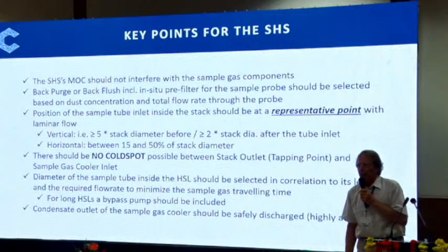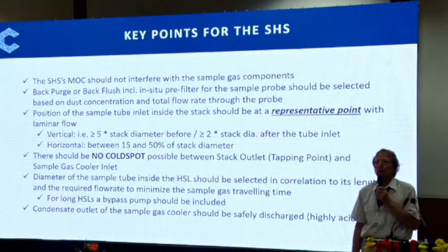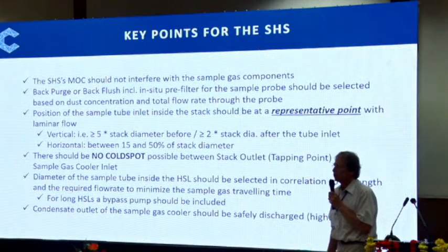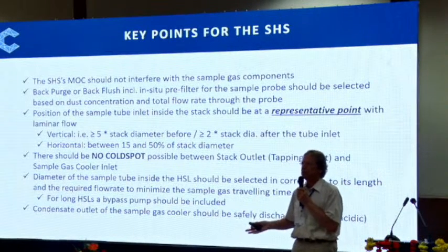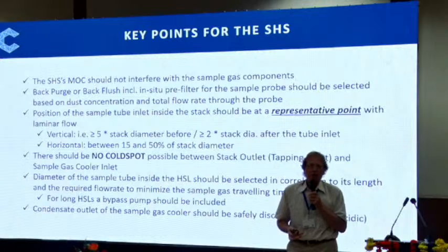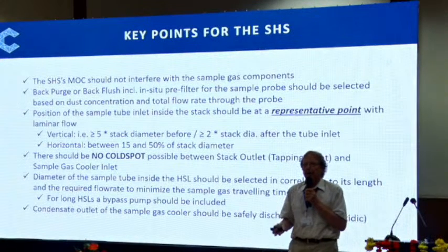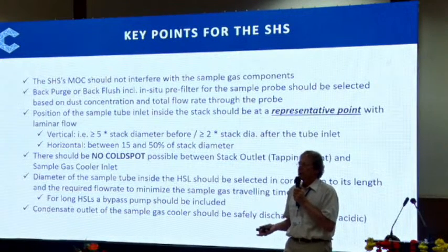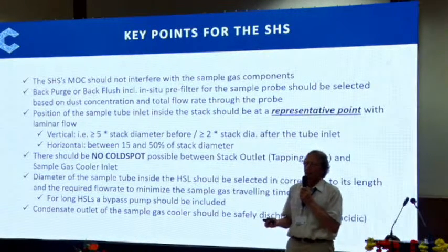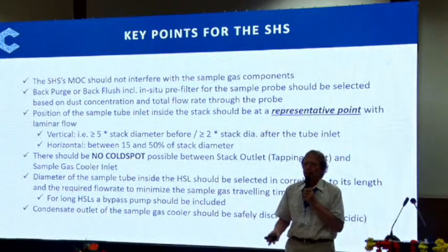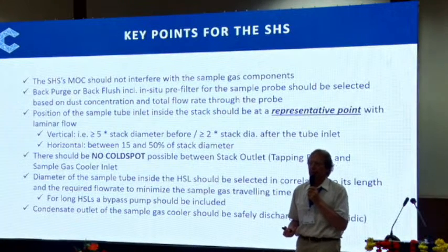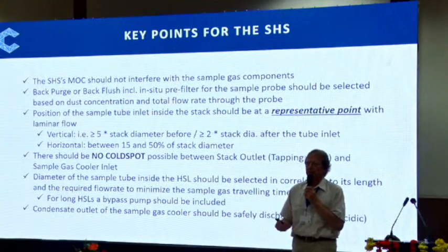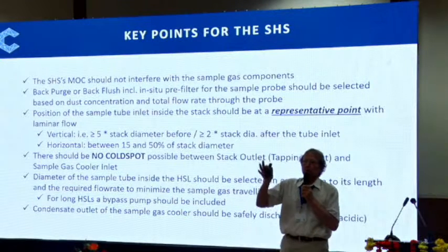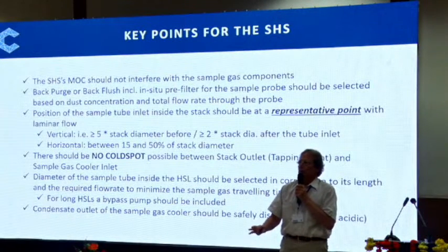Yes, if we have very long heated sample lines, very long umbilicals, because we have a large distance, possibly use a bypass pump and use a higher diameter of umbilical, of the sample transport line in the umbilical, so that you get a higher quantity of gas with this bypass pump down to the analyzers in order to reduce the response time of the overall system.